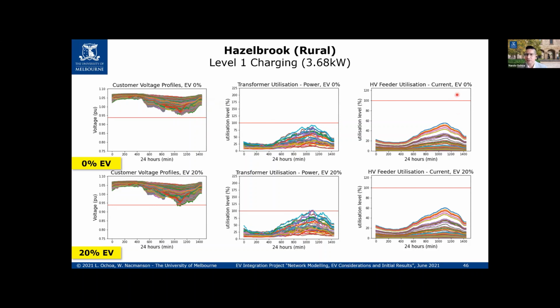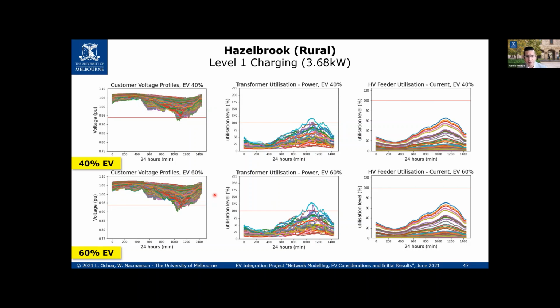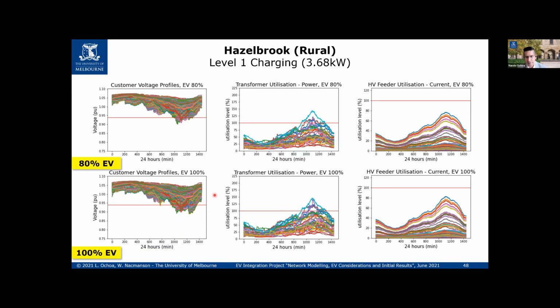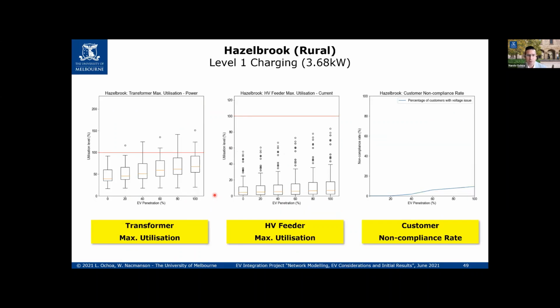In terms of the utilization of the high voltage conductors, they're all fine. But the utilization of the transformers is much higher, because now you have many more transformers with fewer customers per transformer. That means the moment you have electric vehicles, with level 1 charging, you start seeing the limits increasing or being exceeded. This is, of course, worrying.